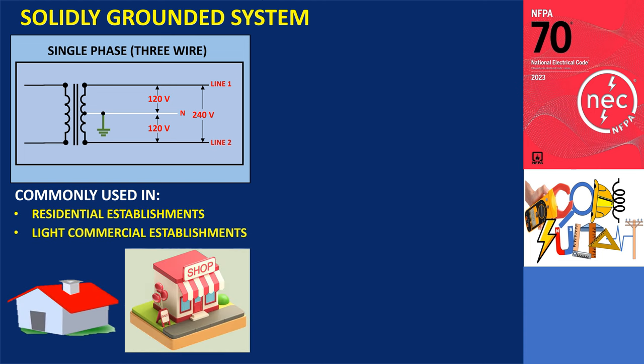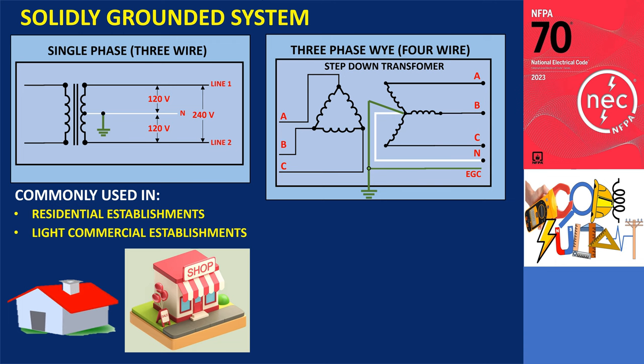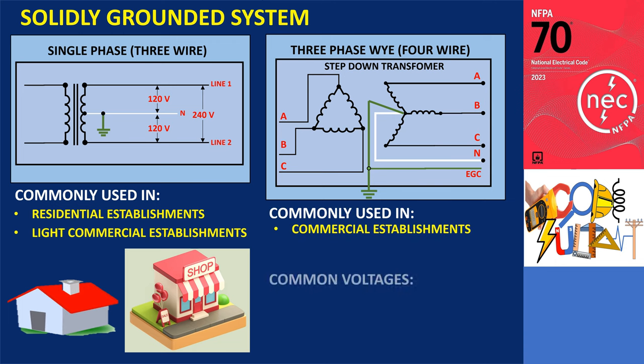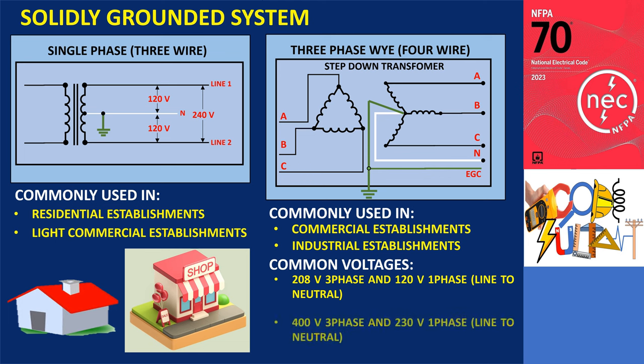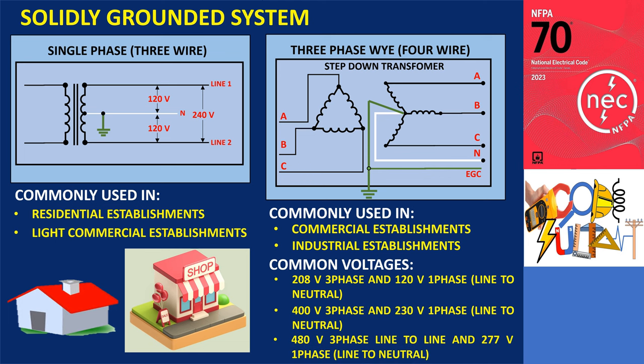Single-phase, three-wire configurations are commonly used in residential and light commercial establishments. The circuit breaker panels typically have two live hot wires and a neutral. Three-phase, four-wire is the most common commercial building electric service, with voltages of 208 volts three-phase and 120 volts single-phase, used to power lighting, small appliance loads, and smaller AC systems. In larger facilities, the voltage can be 480 volts for three-phase and 277 volts for single-phase, where 480 volts is used for larger equipment.